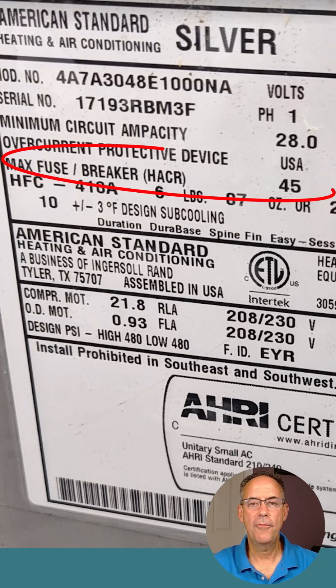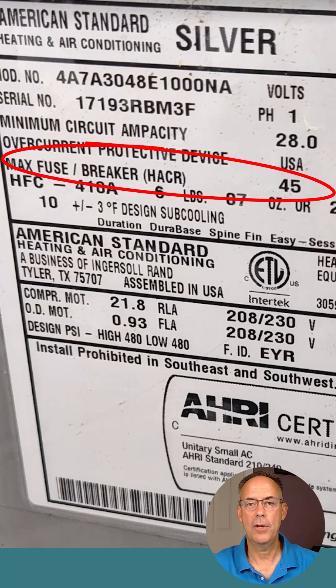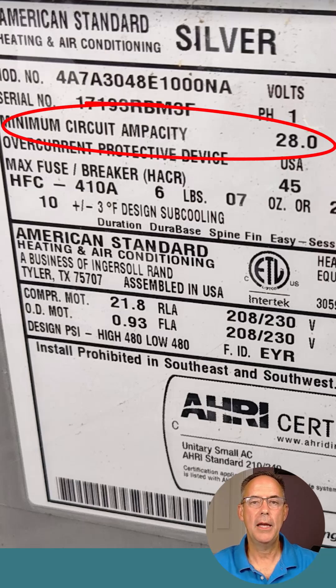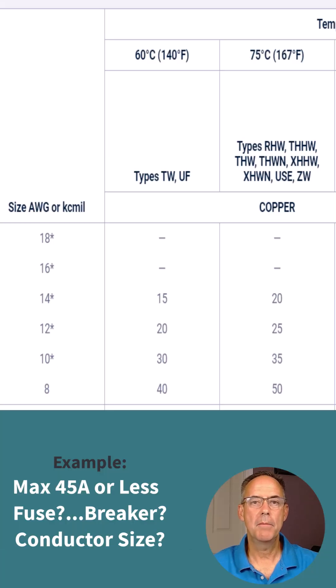On this next tag it tells us maximum fuse/breaker — so you can use either — and it tells us it's 45 amps. Note that you can put in less than 45 if you want to and it meets the manufacturer's requirements; it just can't be more than 45. The minimum circuit ampacity on this unit is 28 amps, so let's go over to Table 310.16 to find the appropriate wire size.